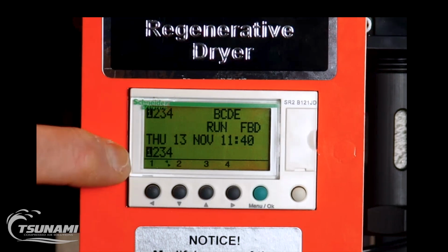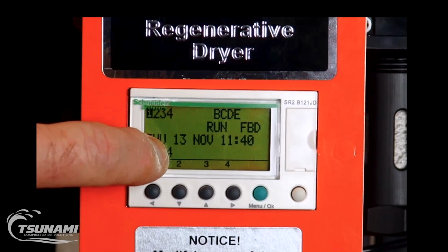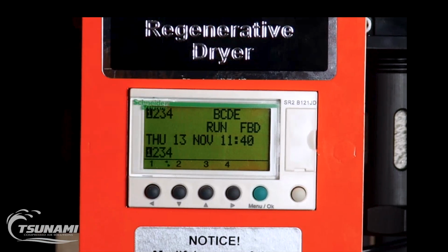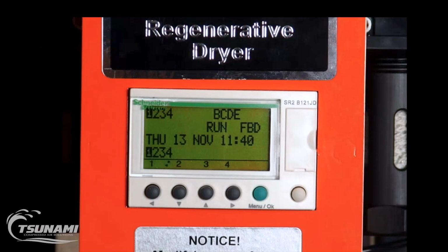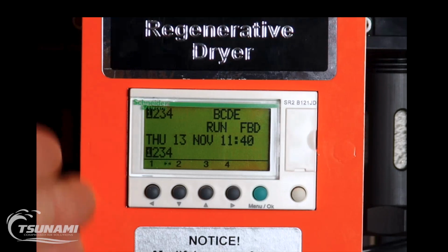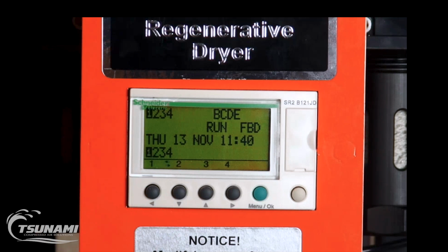So it's going to go from tower 1, regenerate tower 2, and then when it shifts back to tower 1, at that point, it will pause the dryer. In some applications, that's the process that we want to utilize. If I leave this on for about another 3.5 minutes, you will see that it goes from tower 1 to tower 2, back to tower 1, but then it will pause. And then when that signal goes away, it would start up the program all over again.